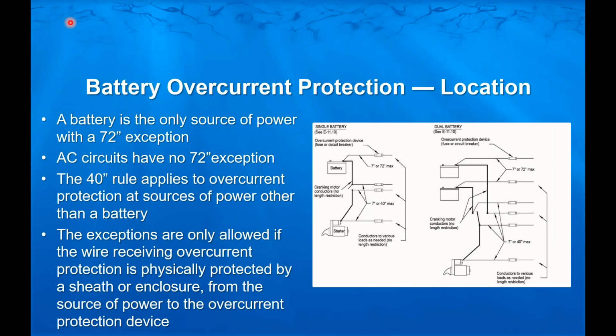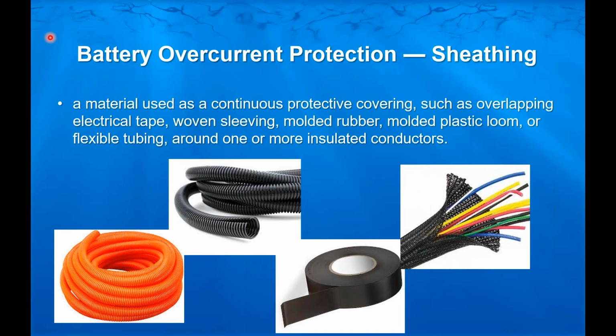And the exceptions are only allowed if the wire receiving overcurrent protection is physically protected by a sheath or enclosure from the source of power to the overcurrent protection device. That sheathing is defined in ABYC Standards as a material used as a continuous protective covering, such as overlapping electrical tape, probably the least preferable of all the options. Woven sleeving, molded rubber, molded plastic loom, or flexible tubing around one or more insulated conductors. So that's the kind of material we need to see around those conductors if you don't get that overcurrent protection within 7 inches.